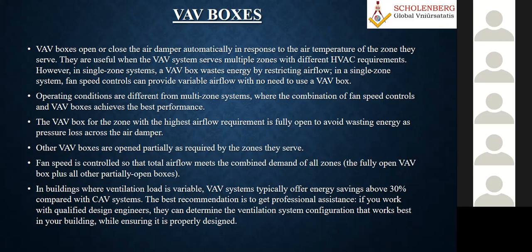Similarly, for these boxes, the zone with the highest airflow requirement is fully open to avoid wasting energy. This is all your programming, you can do that. Some of the other boxes which are very far away can be partially open, depending upon the load required in the zone served. And fan speed is again controlled by variable speed controls. So this type of VAV system definitely offers, as I'm telling you, almost 30% energy saving compared to a constant volume system, particularly in buildings where the load is highly variable.